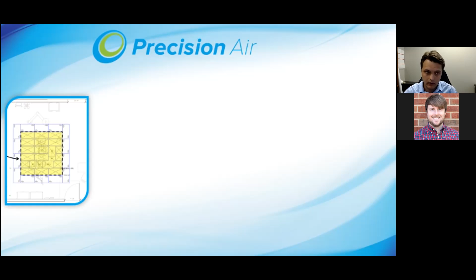What's going on behind the curtain is we look at the room and where some boom locations might be, and provide a design that first and foremost protects the patient as much as possible. We'll check the box of complying with ASHRAE 170, but designing strictly to that minimum really doesn't provide any patient protection at all—you might as well not have laminar flow. So we'll check that box, but also make sure we're providing as much actual patient protection as possible.